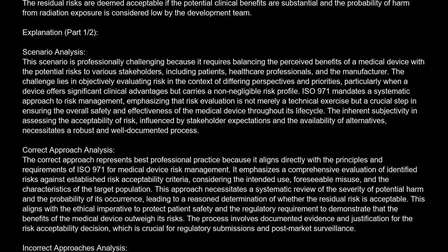This approach necessitates a systematic review of the severity of potential harm and the probability of its occurrence, leading to a reasoned determination of whether the residual risk is acceptable. This aligns with the ethical imperative to protect patient safety and the regulatory requirement to demonstrate that the benefits of the medical device outweigh its risks. The process involves documented evidence and justification for the risk acceptability decision, which is crucial for regulatory submissions and post-market surveillance.